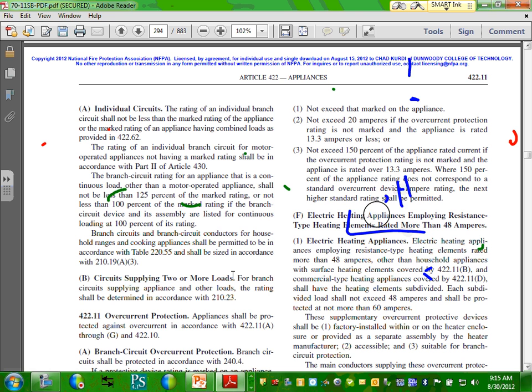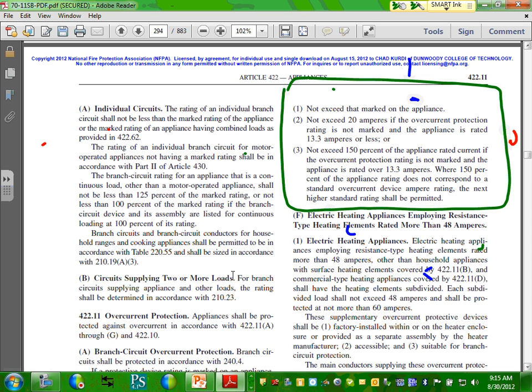I would like you guys to look at this, please, and keep it for future use. Appliances. Here's what I would like you to highlight. This section here. Now, what is the definition of appliance? They define the appliance, guys, as any equipment that is commercially available, manufactured for use. For example, a water heater is an appliance, a dishwasher is an appliance. So commercially available. Industrial machines are not appliances, okay? So for appliances, not to exceed the rating marked on the appliance. First of all, is it marked on the appliance? Don't exceed it. If it's not, and the full load amp is 13 or less, don't put smaller than 20 amps. That's when you guys sized the garbage disposal. What did we say? 20 amps. When we sized also the garbage disposal and dishwasher. When we sized the dishwasher, what did we say? 20 amps. Because the full load amps is 13 or less, 20 amps, no question asked. Can I have thumbs up, Chad? We got that one? Cool.